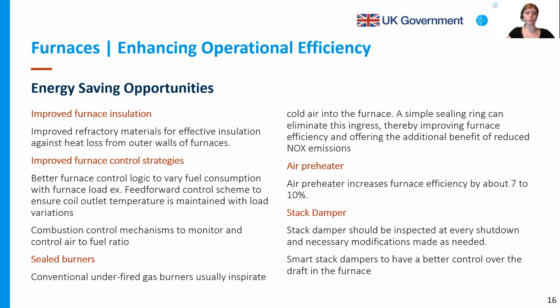Of course, another control should be to control the air-fuel ratio to ensure complete combustion. This is something that we all are very familiar with. Too much excess air leads to low flame temperature. In order to heat up this excess air, a great volume of air, the combustion chamber needs to burn more fuel to achieve the required heat. And of course, incomplete combustion, on the other hand, leads to loss of unburned fuel in the flue gas. So either way, you tend to lose fuel. So it's very important to establish a strong control over your air to fuel ratio.